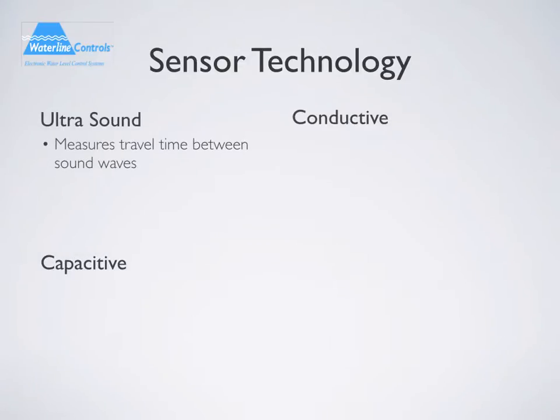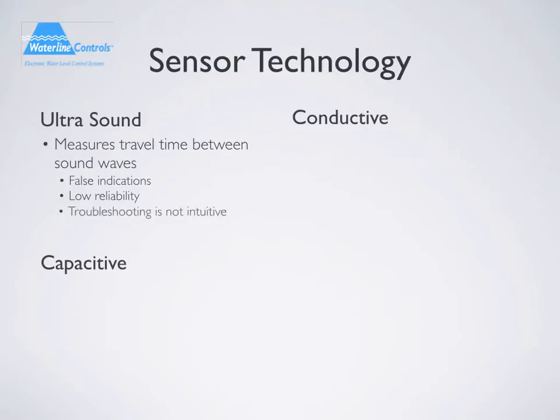Ultrasound technology is the process of reflecting sound off the surface of the water and using time to determine the water level. This method can give false indications and triggers caused by the reflective nature of water and the walls. Foaming of the water in a cooling tower can also cause an ultrasound sensor to report false levels. When this technology needs to be serviced, troubleshooting is not intuitive for the technician since nothing touches the water, and the technician will need to electrically connect into the sensor to troubleshoot it.